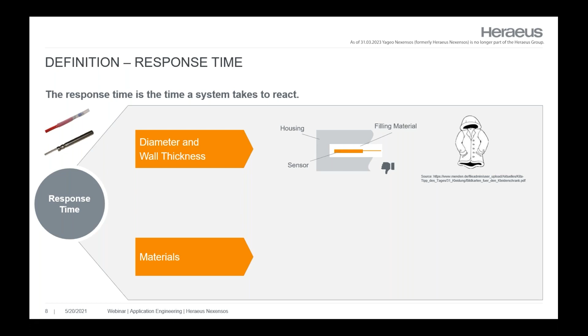So here you can see again in the drawing that there's less material around our sensor element. So you can say in general, to achieve a better response time, the diameter should be small and the wall thickness should be thin.